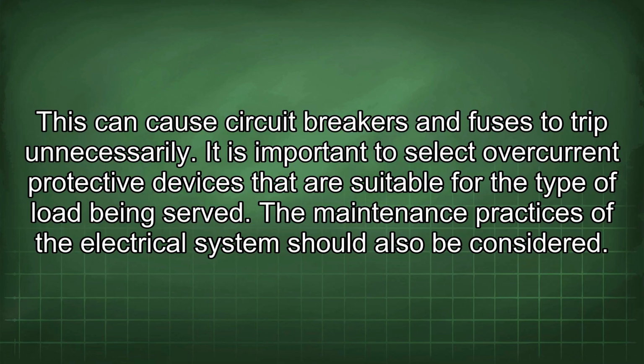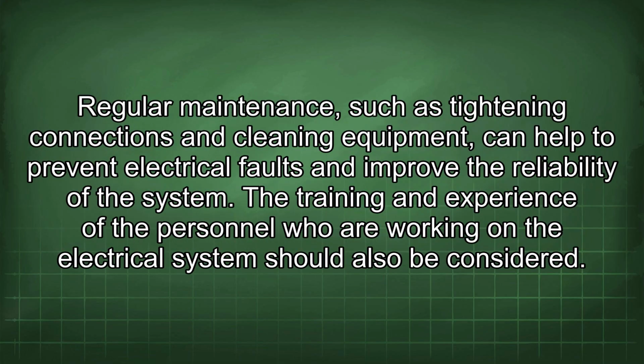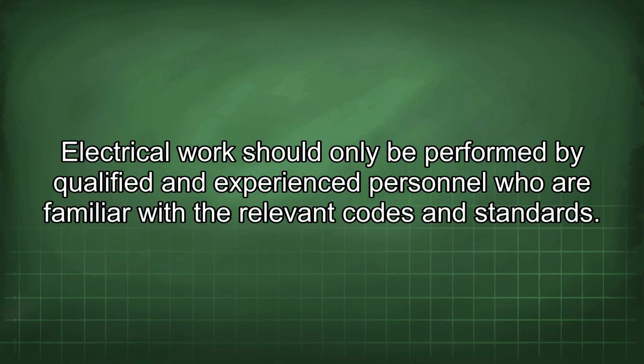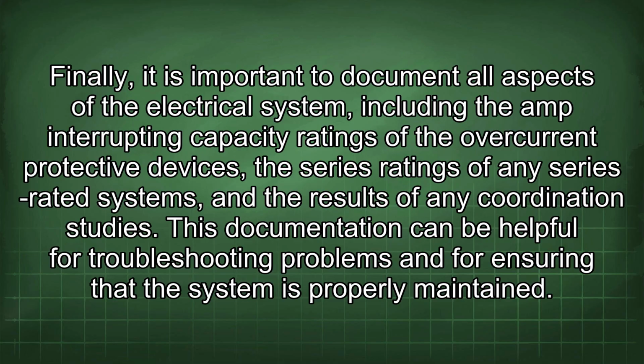The maintenance practices of the electrical system should also be considered. Regular maintenance, such as tightening connections and cleaning equipment, can help to prevent electrical faults and improve the reliability of the system. The training and experience of the personnel who are working on the electrical system should also be considered. Electrical work should only be performed by qualified and experienced personnel who are familiar with the relevant codes and standards. Finally, it is important to document all aspects of the electrical system, including the amp interrupting capacity ratings of the overcurrent protective devices, the series ratings of any series-rated systems, and the results of any coordination studies. This documentation can be helpful for troubleshooting problems and for ensuring that the system is properly maintained.